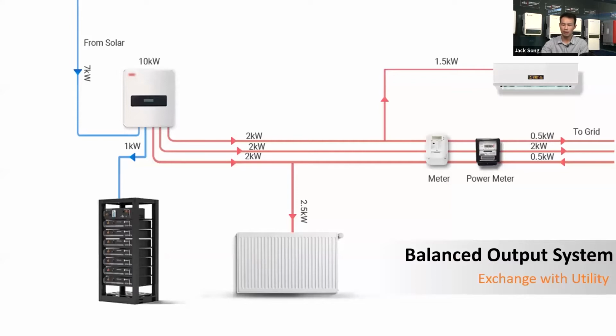And here is the first scenario. Before we talk about the benefits of unbalanced outputs in this picture, we give a general introduction about the traditional output of 3 phase. We call it balanced output. Balanced output means that on the output side of the inverter, each phase has to output the same power. Like here, we have a 10 kilowatt inverter, but from PV we have 7 kilowatts, and 1 kilowatt charges the battery. So the inverter will output 6 kilowatts on the AC side. 6 kilowatts means on each phase you have to output 2 kilowatts, balanced. So this is what we call the balanced output.